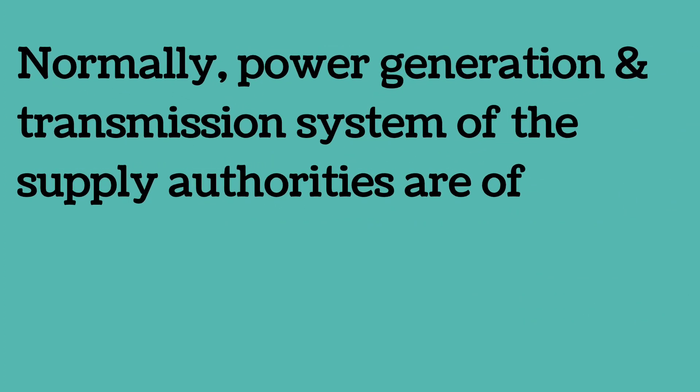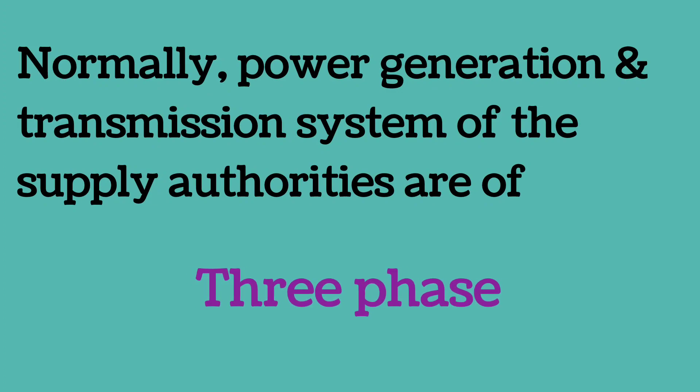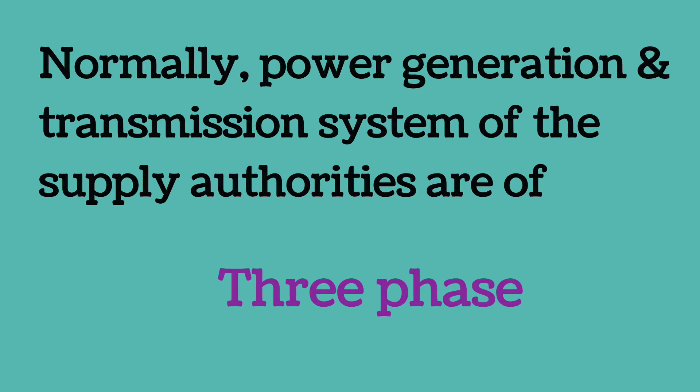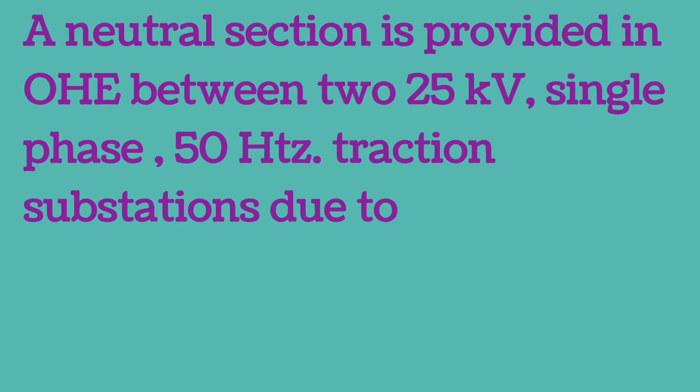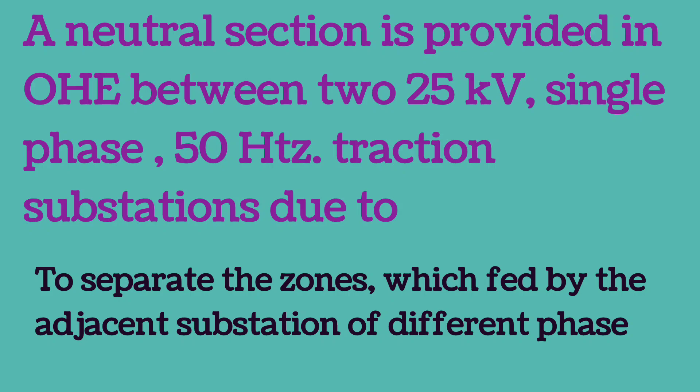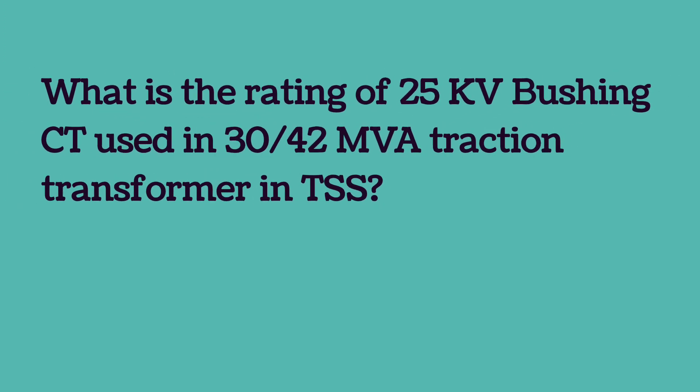Normally, the power generation and transmission system of the supply authorities are of 3 phase. A neutral section is provided in the OHE between two 25 kV single phase 50 Hz traction substations in order to separate the zones which are fed by adjacent substations of different phase.